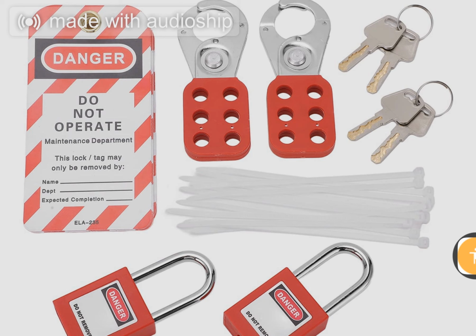Exactly. Then step two, you go to the circuit you're about to work on and test it. And hopefully it shows 0 volts. Okay, but the big fear is, what if the meter broke between testing the live source and testing my circuit? And that is precisely why there's a step three. You immediately go back to that known live source and test it again. So you close the loop. You close the loop. If it reads live again, you've just verified three things. Your meter worked at the start, the equipment is de-energized, and your meter didn't fail in between. It removes any shadow of a doubt. It's a beautifully simple closed-loop safety system.